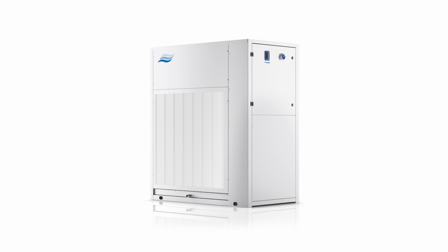Both types of dehumidifier will actually add heat to the air during the drying process. So the next question to ask is, how sensitive is the area to heat gain? Now, when water changes its state from a gas, as it is in the air, to a liquid, which is what the dehumidifier is doing, the thermodynamic process results in around 0.63 kilowatts of heat being generated for every kilo of moisture removed. Think of it as evaporative cooling in reverse.